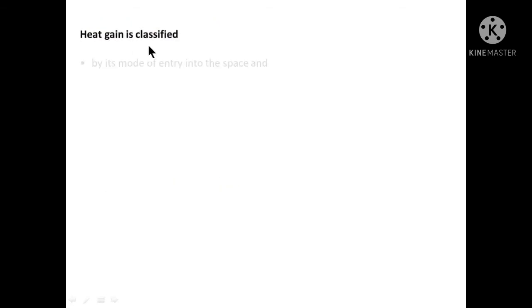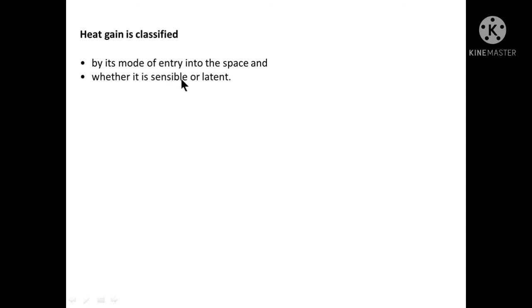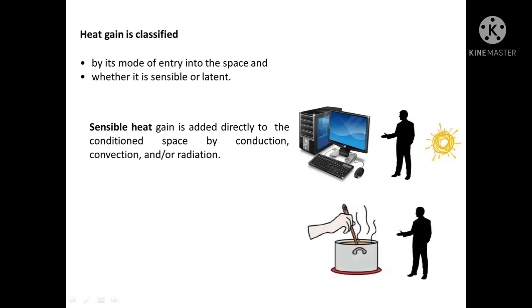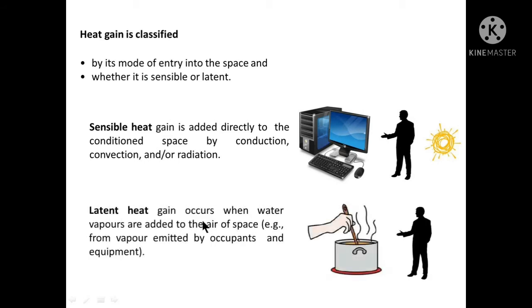Heat gain is classified in two categories: first by its mode of entry into the space, and second whether it is sensible or latent heat. Sensible heat is the heat which is directly added to the conditioned space by conduction, convection, and/or radiation. Whereas latent heat is the gain which occurs when water vapors are added to the air of the space, for example from vapors emitted by occupants and equipment.